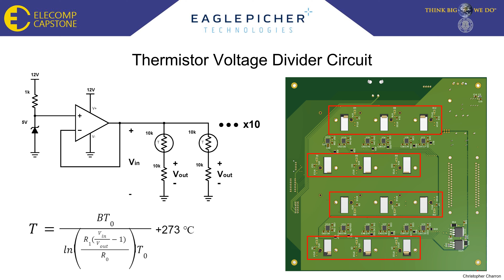The 12 thermistor voltage dividers are located at the bottom of the board next to each of the cell negative terminals. A cutout is made in the board to allow the thermistors to be positioned to touch the cell and ensure the most accurate measurement. The thermistors used by the BMS are located in the same manner, however no extra circuitry is required on the board.